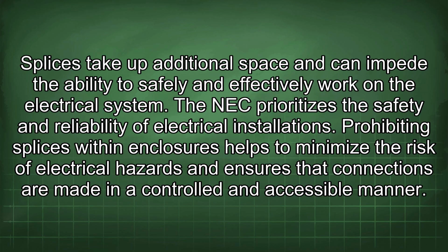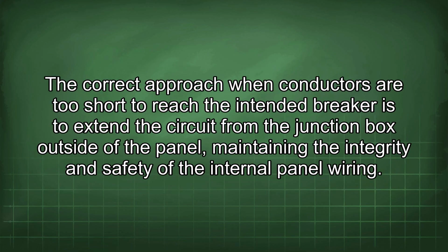controlled and accessible manner. The correct approach when conductors are too short to reach the intended breaker is to extend the circuit from the junction box outside of the panel, maintaining the integrity and safety of the internal panel wiring.